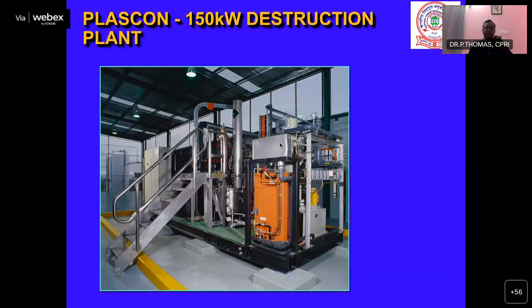Here, I would like to bring to your kind notice that suppose you have a transformer of, say, 20,000 ppm or 10,000 ppm. You may think that we can remove the oil, put in some new oil, wash it and put it back into the system. But what we found from the studies is that with oil having 10,000 ppm and above, if you try to do that, after 5 or 6 months the PCBs come back into the oil. Say you remove the 10,000 ppm oil, clean with fresh oil and put back new oil to use the transformer. Then the oil will still be contaminated with PCBs. Everything should be less than 2 ppm, but it will be more than 50 ppm. That's the reason we found that anything more than 10,000 ppm, the transformer has to be totally destroyed.